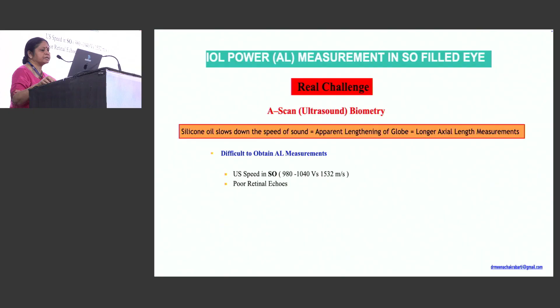When there is silicone oil in the eye, it slows down the speed of the ultrasound and there is apparent lengthening of the globe, and hence you erroneously measure a longer axial length. The speed of the ultrasound in silicone oil depends upon the viscosity of the silicone oil that you have implanted. When you are operating on a patient who has undergone surgery elsewhere, they usually do not specify the centistokes of silicone oil used. But commonly in most centers, we use 1,000 centistokes silicone oil. And the ultrasound speed is around 980 meters per second compared to 1,532 meters per second in the normal vitreous. So there is that much slowing of ultrasound speed.